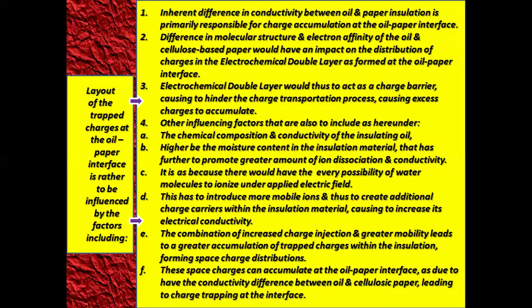Higher moisture content in the insulation material further promotes a greater amount of ion dissociation and conductivity. C, there is every possibility of water molecules ionizing under an applied electric field. D, this introduces more mobile ions and thus creates additional charge carriers within the insulation material, increasing its electrical conductivity.